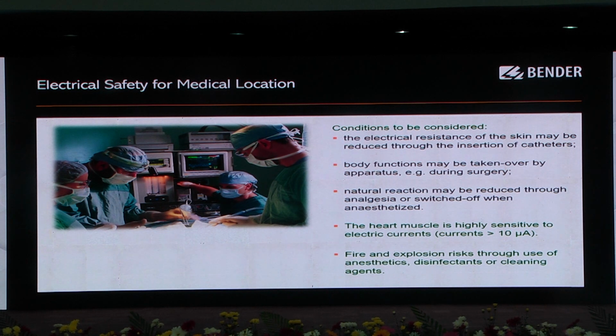That is the reason in the ICU and OT they do not provide ELCB or RCCB; they bypass them. We have seen this in many hospitals due to nuisance tripping. That is the reason you have to use an unearthed system in the group 2 location.